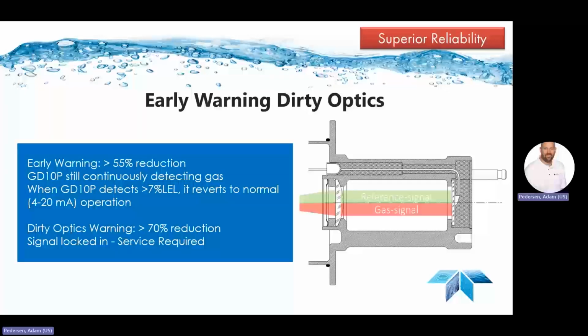If the device isn't cleaned and contamination continues to build, the infrared absorption reduces to 70% of its calibration level, and the device will then go to a 1 milliamp output, which will indicate a genuine fault condition. In this state, the device is no longer detecting and needs to be taken offline.